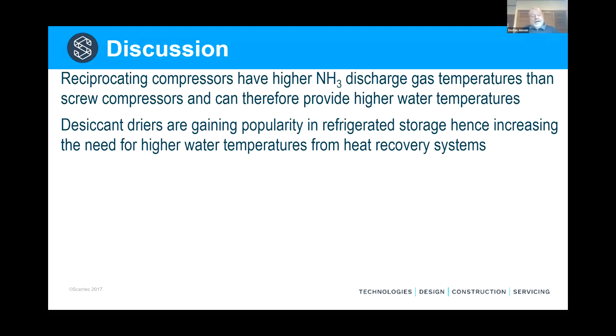Desiccant dryers are gaining popularity for a whole bunch of reasons. The main reason being the prevention of slippery floors. Other reasons are extending the defrost intervals, so that we have more hours between each defrost. Improvement in product quality, we don't have any frost settling down on the product, and quite often the product is barcoded. Frost on the product prevents you from reading the barcode. And large-scale ASRS system, automatic storage and retrieval systems for boxes, the meat and cartons and the like, they require dew points that are sometimes below minus 30, because otherwise their automatic retrieval system simply do not work. So this is an application that's coming more and more.